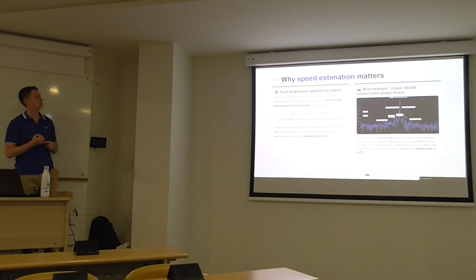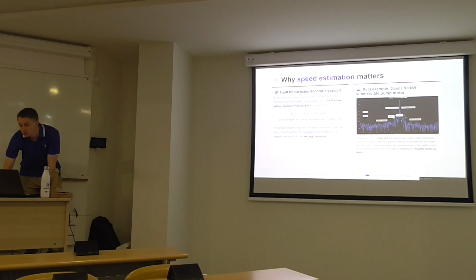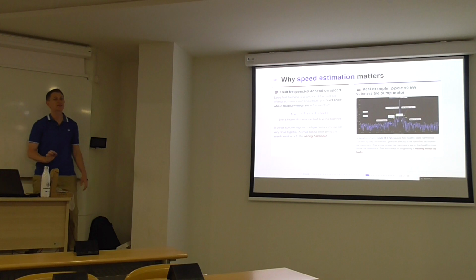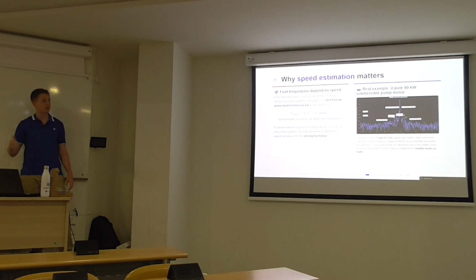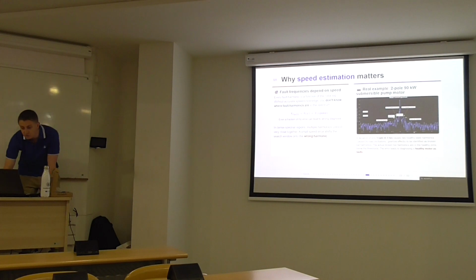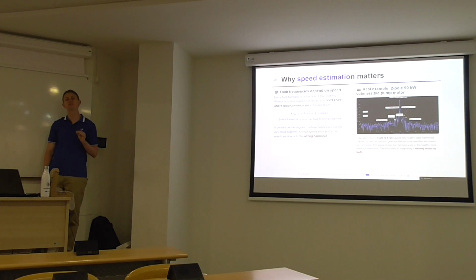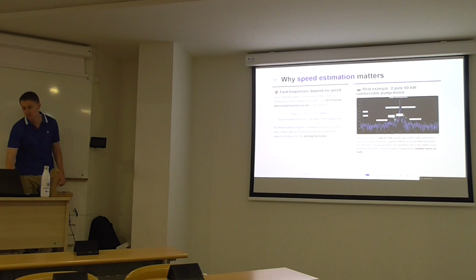And here you have an example. Again, a real example: a 2-pole, 90 kilowatt submersible motor. So what do we have here? The fundamental component, then 2 sidebands which are related to load oscillation, not a fault, and other sidebands which are related to broken bar faults. See how close those sidebands are. They are separated by 0.1 Hz. That means that in this motor, a deviation of only 3 revolutions per minute over the 3000 at which this motor is rotating can translate into a wrong diagnosis. I mean, they are so close. It's just 0.1 Hz. I could think that the broken rotor bar harmonic is this one instead of that one. Okay? So accurate speed estimation is super important, just to know exactly where my harmonic is.